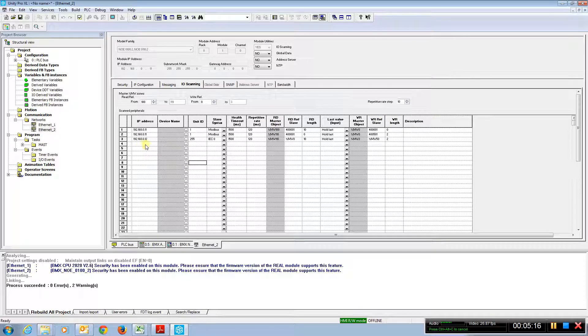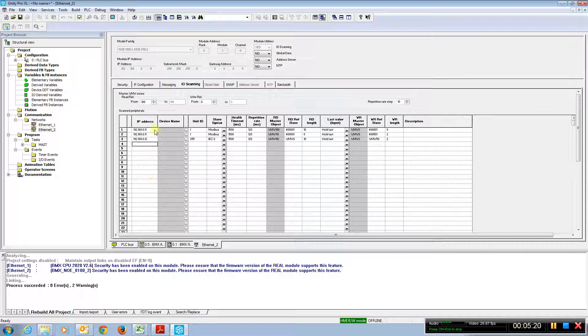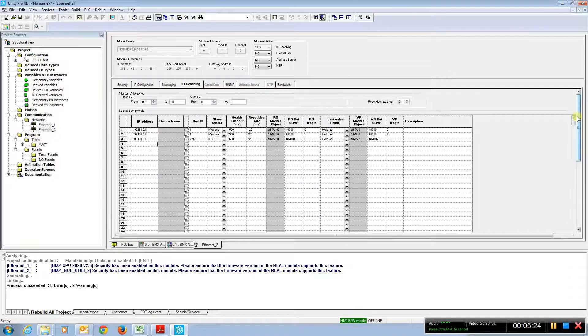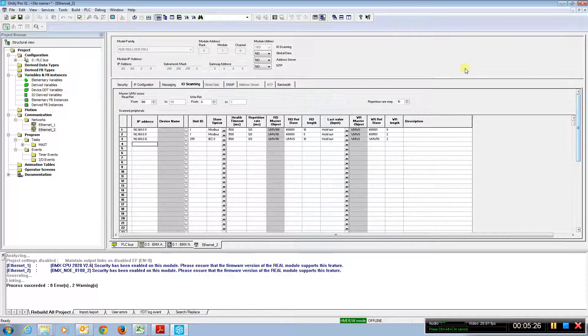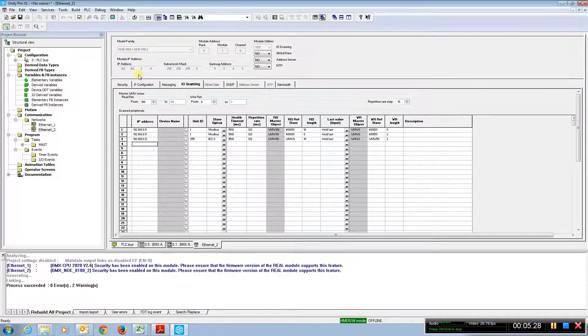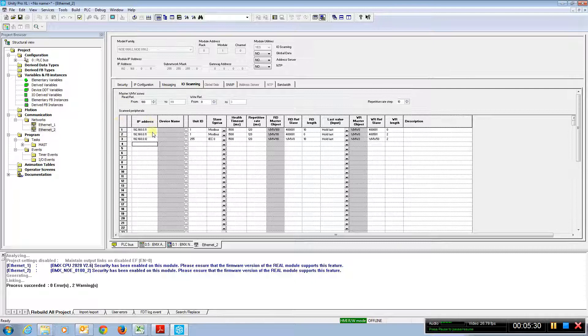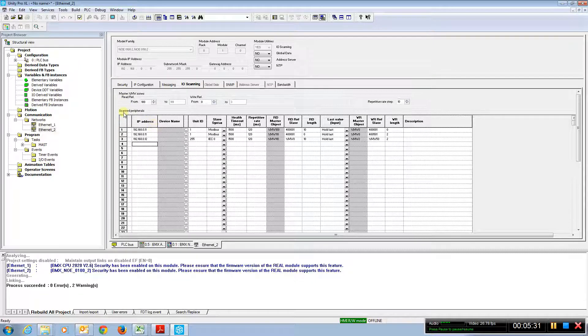Modbus IO scanning like this isn't perfect for every application. It does leave a socket wide open at all times with ethernet connections. And some third party devices don't necessarily like that. So this is a very easy way of programming communications to a device.